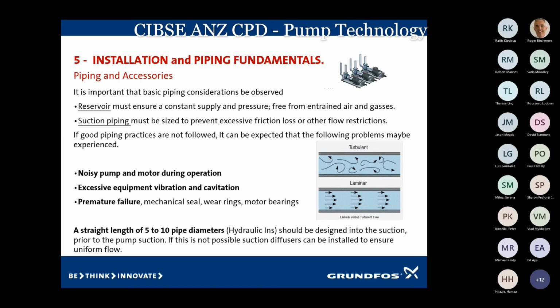So we need to have 5 to 10 pipe diameters of straight pipe coming into the pump. So if it's a 100 mil connection, we want 500 to a meter of straight pipe. That way, when the water enters into the pump, it's nice and smooth. The pump can take that water and discharge it out, and it's quite happy.